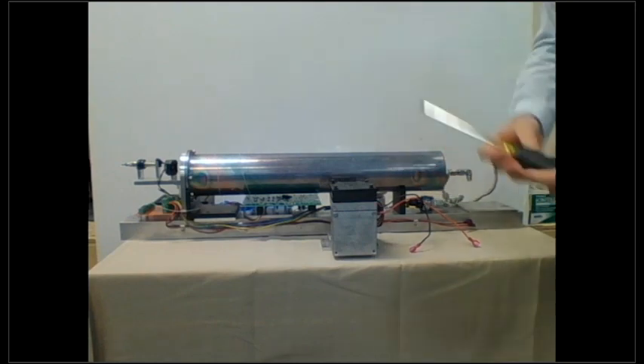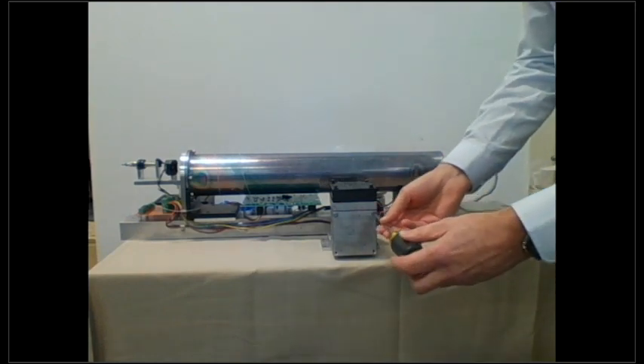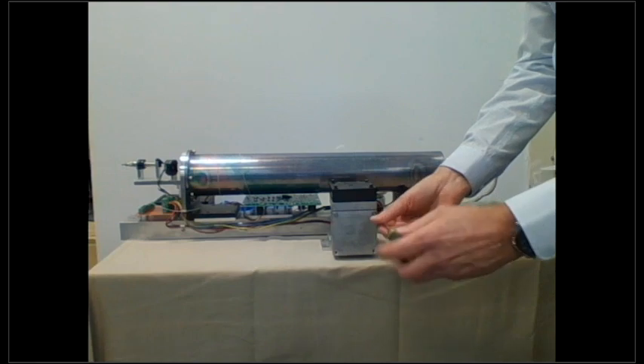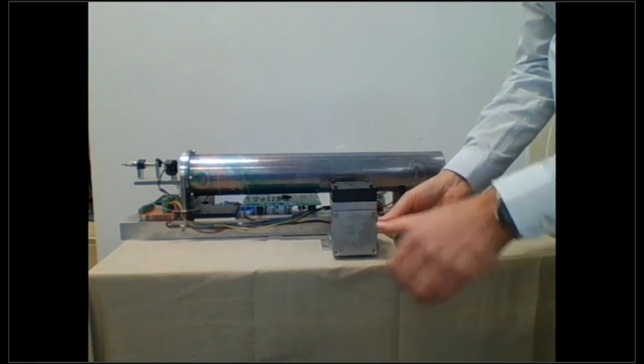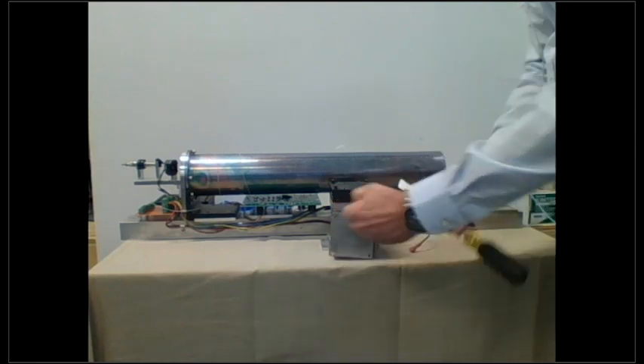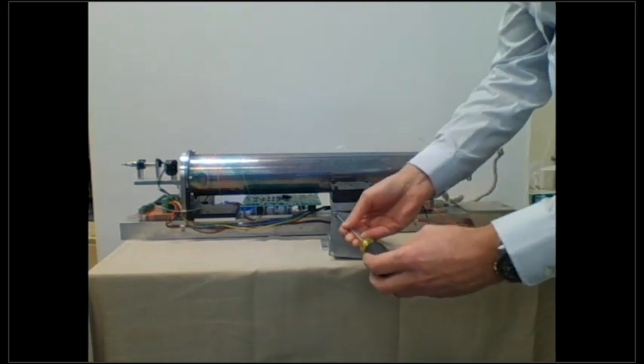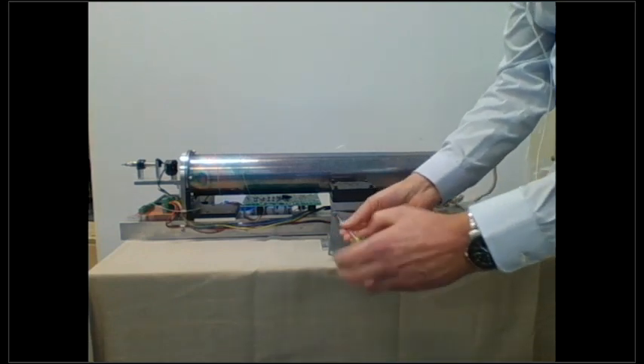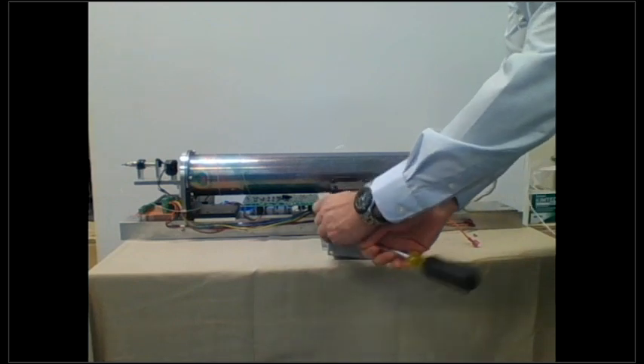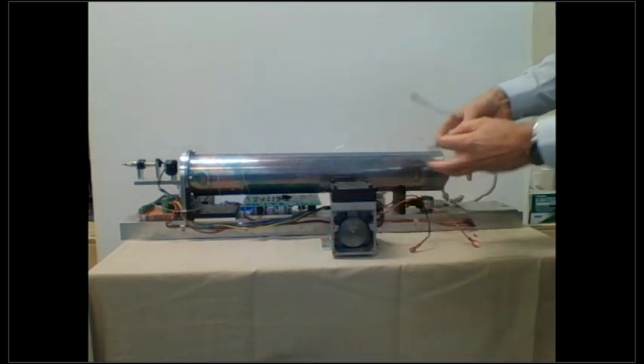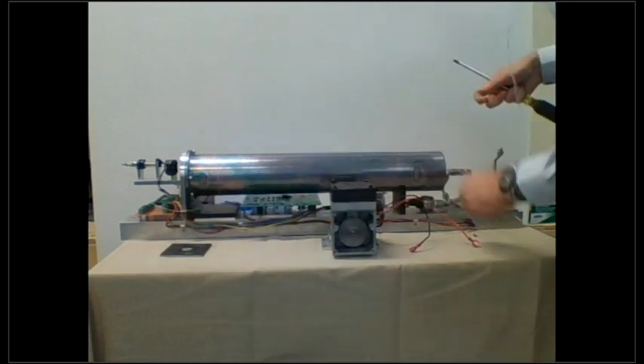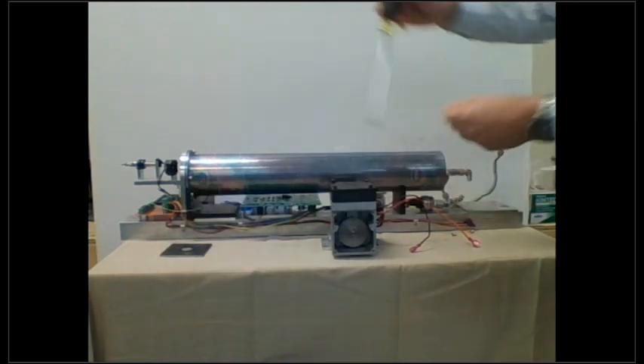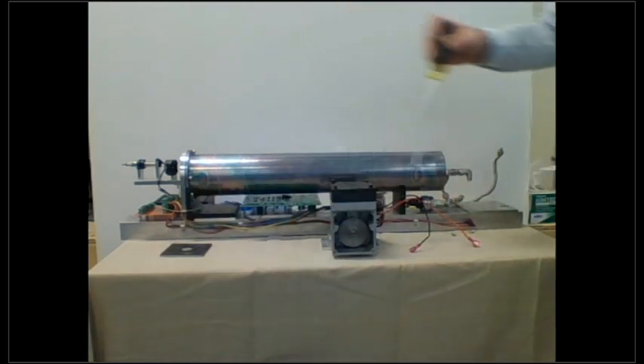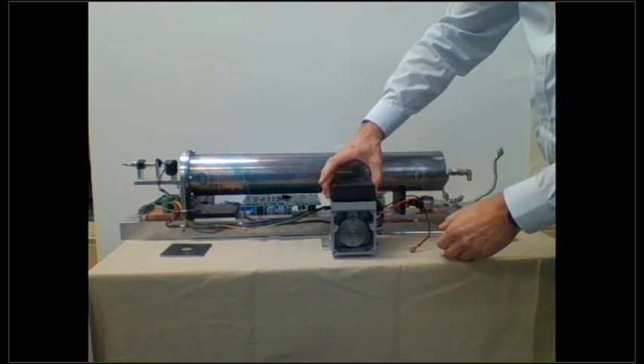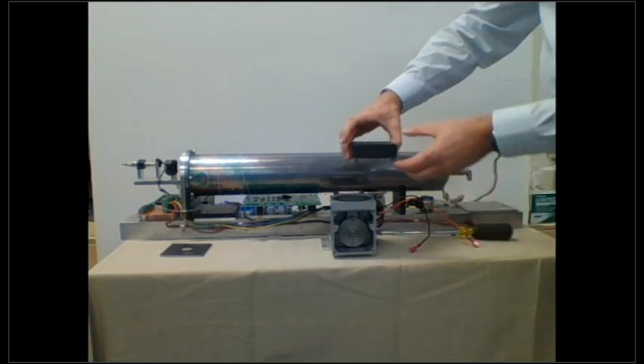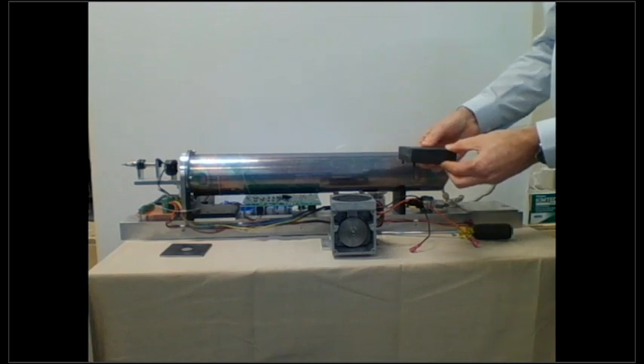So the first thing that you need to do is just remove this little panel on the front of the pump. This gives you access to the actual rotor. So when you take that panel off, there's 4 screws on the top of the pump that hold the pump head in place. I've already loosened them off, so you just simply take them and pull them apart. And the entire pump head comes off. You can set that aside for a moment.